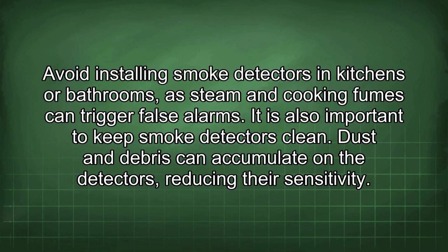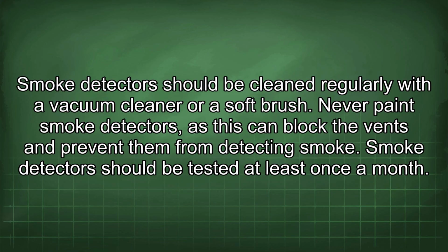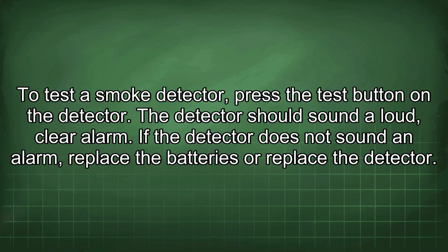It is also important to keep smoke detectors clean. Dust and debris can accumulate on the detectors, reducing their sensitivity. Smoke detectors should be cleaned regularly with a vacuum cleaner or soft brush. Never paint smoke detectors, as this can block the vents and prevent them from detecting smoke. Smoke detectors should be tested at least once a month. To test a smoke detector, press the test button on the detector. The detector should sound a loud, clear alarm. If the detector does not sound an alarm, replace the batteries or replace the detector.